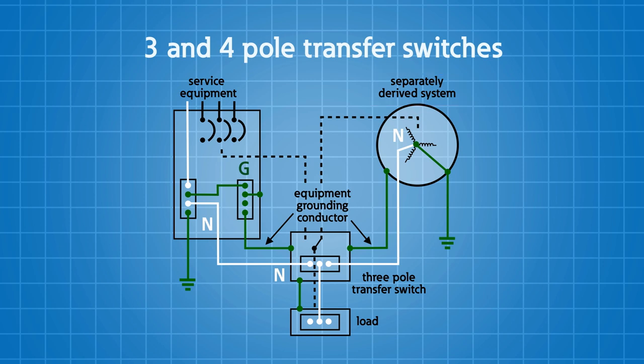So when I have a neutral conductor bonded and grounded in two separately derived systems - remember, I have it grounded and bonded in my service panel and in my generator - I need to make sure that I only have one place where that occurs.